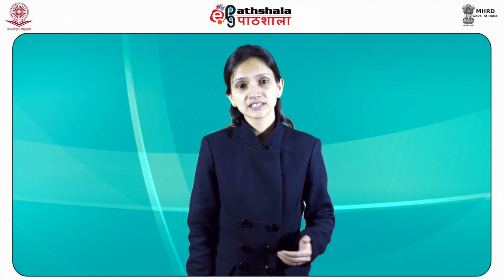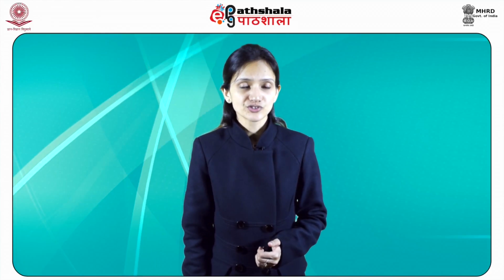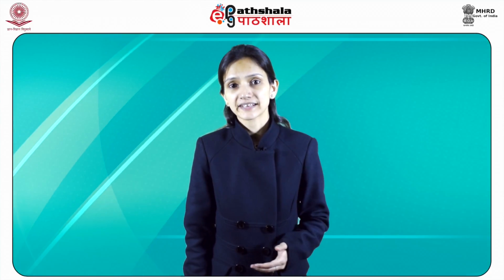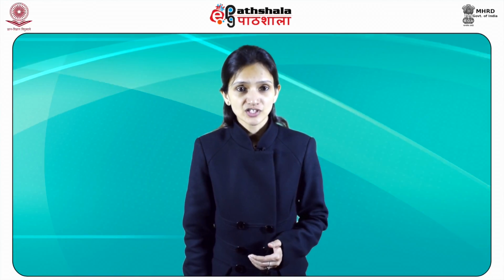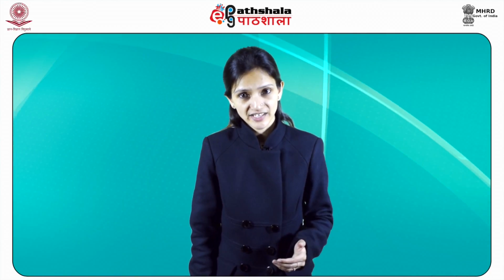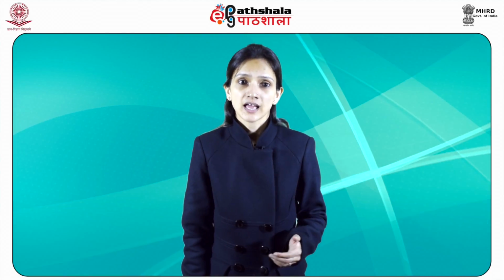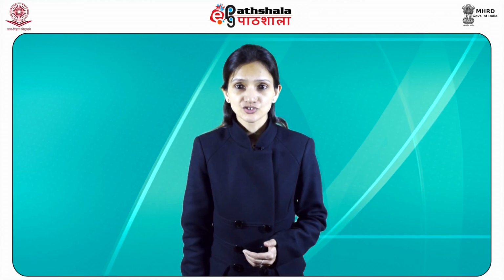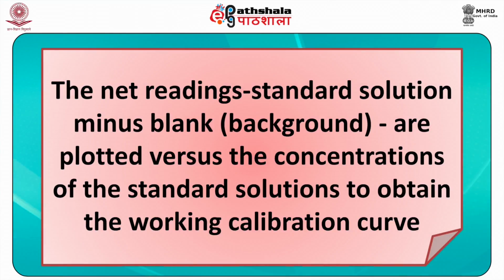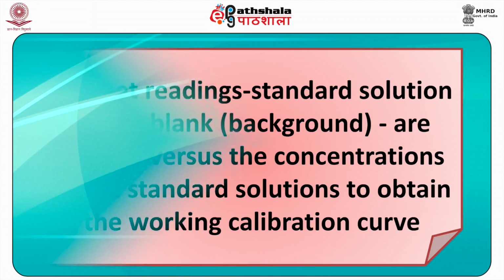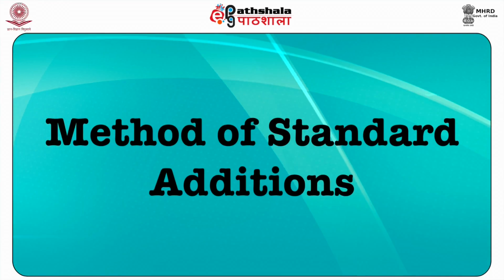In the analytical or working curve technique, a series of standard solutions containing known concentrations of the analyte are prepared. These solutions should cover the concentration range of interest and have a matrix composition as similar to that of the sample solutions as possible. A blank solution containing only the solvent matrix is also analyzed, and the net readings, standard solution minus blank, that is the background, are plotted versus the concentrations of the standard solutions to obtain the working calibration curve. Next is method of standard additions.